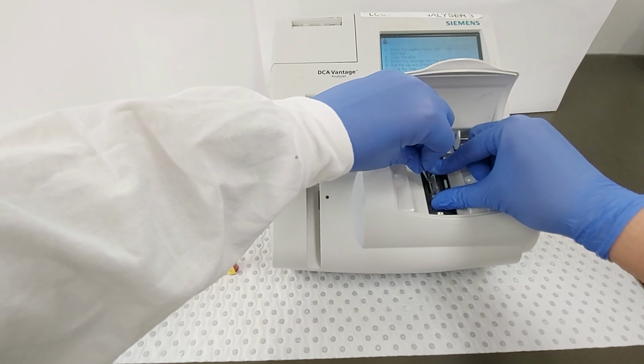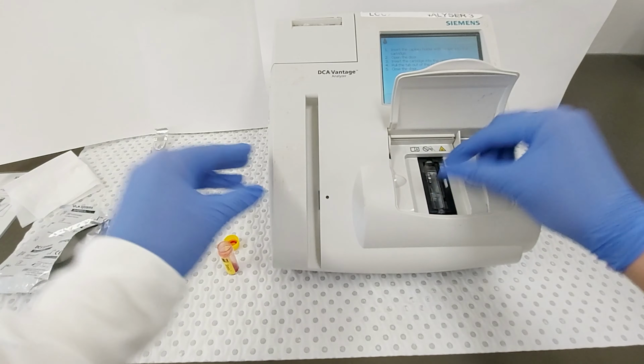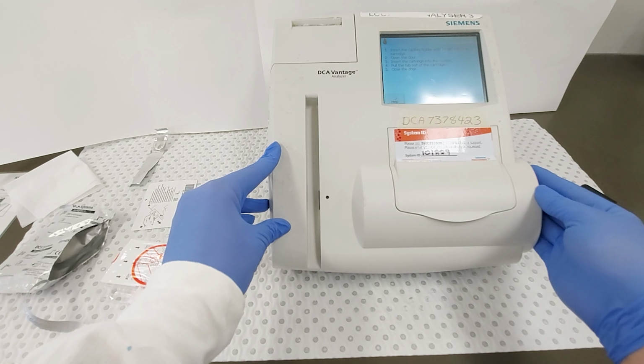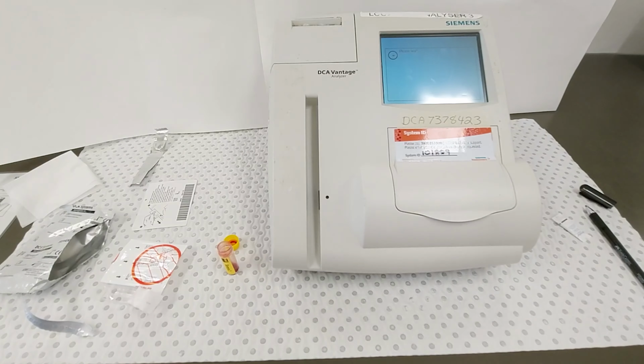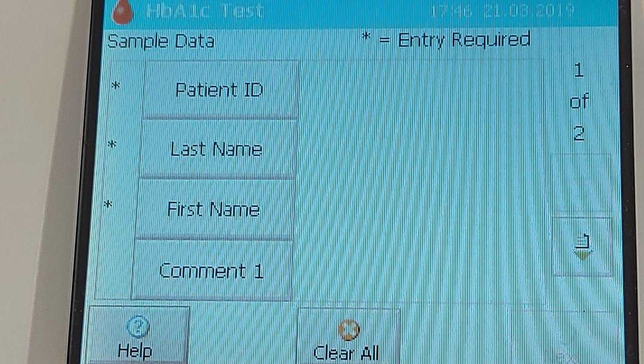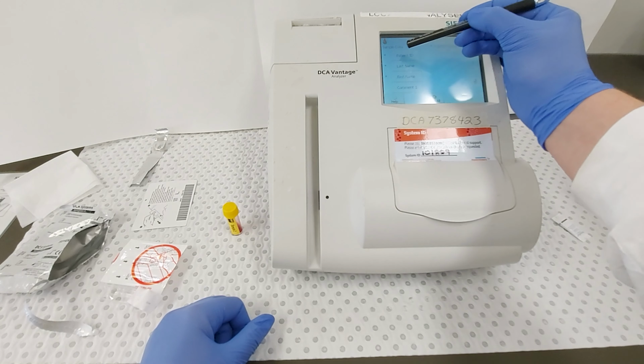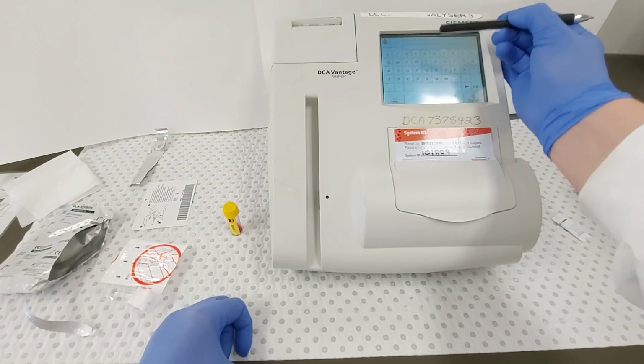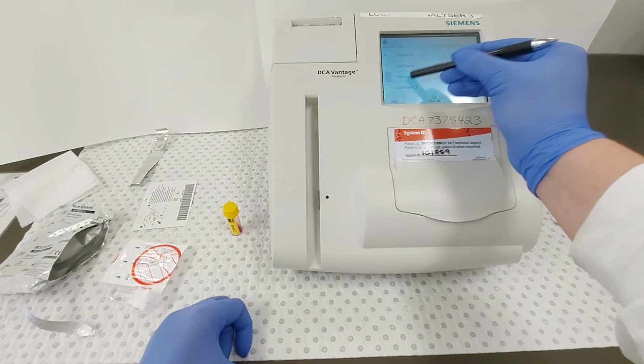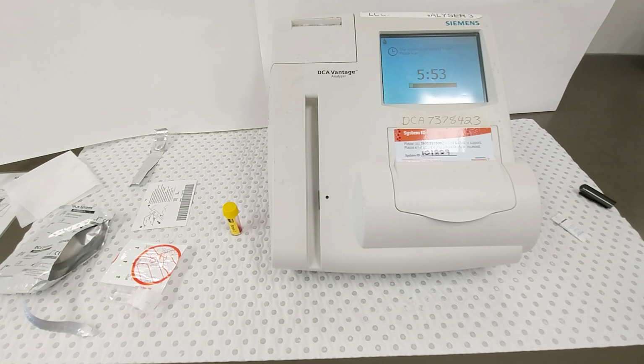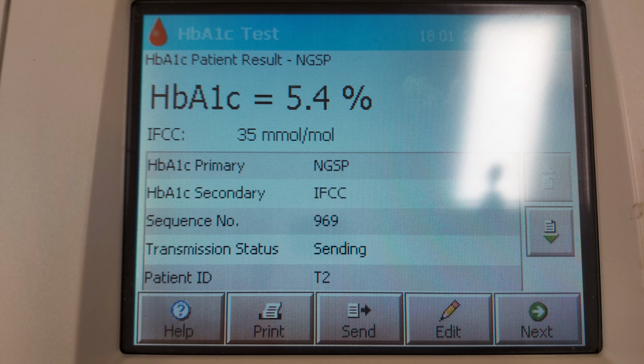Holding the edges of the cartridge firmly, pull the foil tab out of the reagent cartridge and close the reagent cartridge compartment door. The Vantage will now prompt you to add the minimum requirements for patient details, including patient ID, last name, first name, and any comments you may like to include. Once the fields with asterisks have been filled, hit OK to accept and wait for the countdown timer to finish to read the results display.